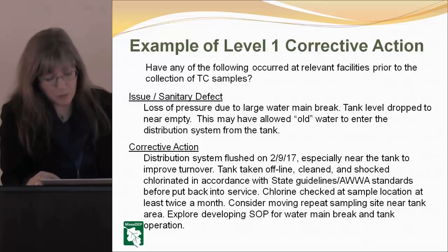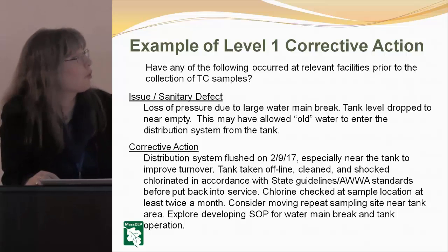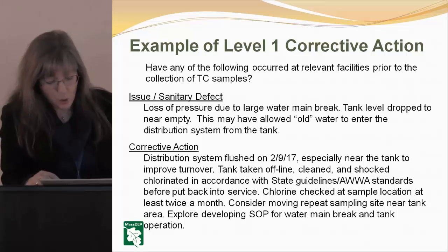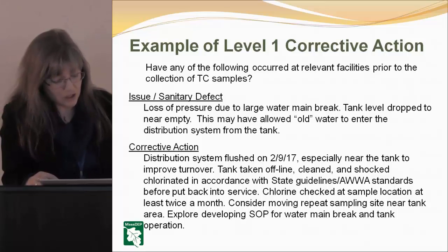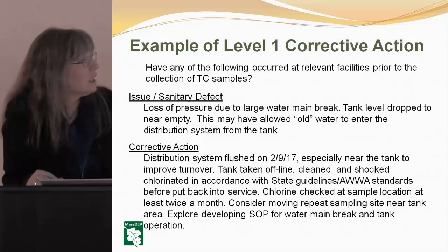Corrective action would be the distribution system was flushed, especially near the tank, to improve the turnover. The tank was taken offline, cleaned, and shock chlorinated in accordance with state guidelines and the AWWA standards before putting it back in service. Chlorine will be checked at sample locations at least 2 times per month.